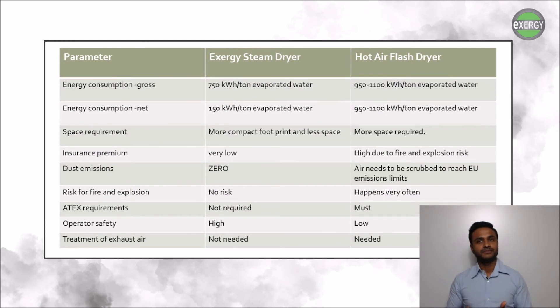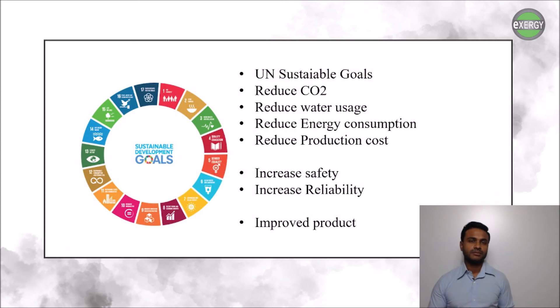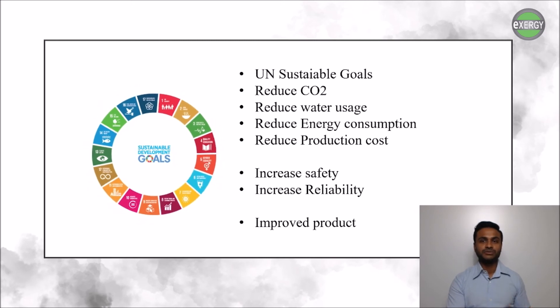There are more advantages to using the Exergy Steam Dryer rather than traditional dryers. The net energy consumption is only 150 kilowatt-hours for every ton of water that is evaporated. There is no fire or explosion risk, creating a safer environment for those working around it. And one of the biggest arguments for the Exergy Steam Dryer is that there is no air emission from the dryer itself.